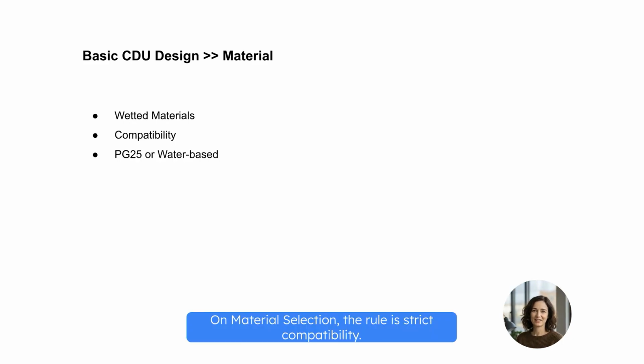On material selection, the rule is strict compatibility. Every component touching the fluid, what we call the wetted materials, must be chemically neutral to the coolant to prevent galvanic corrosion. Don't guess here. Refer directly to the OCP database. They have specific approved lists for both propylene glycol and water-based systems. This is your baseline for safety and environmental compliance.